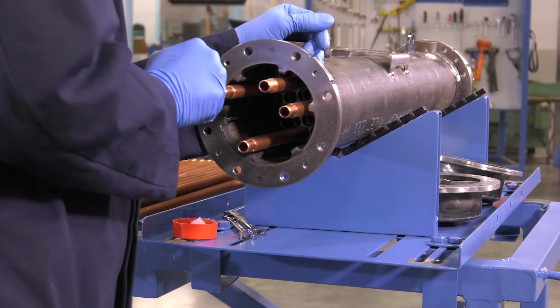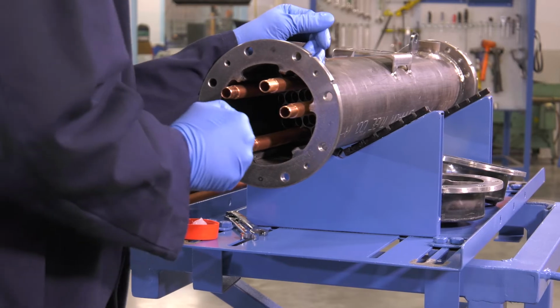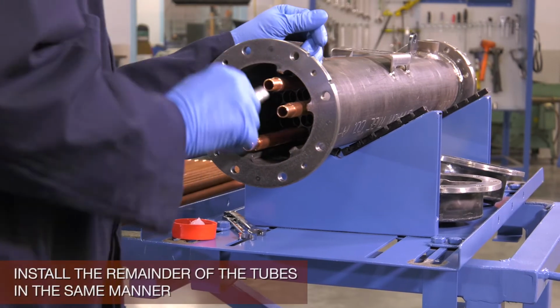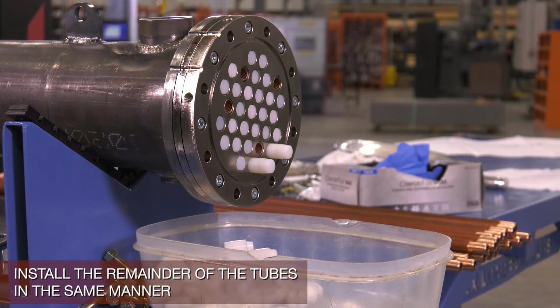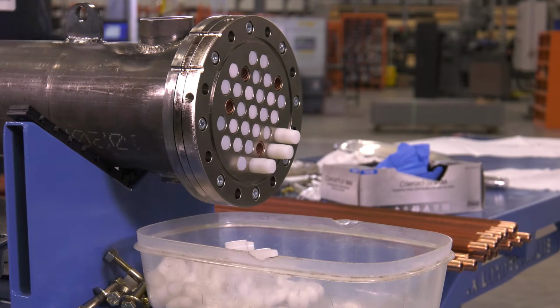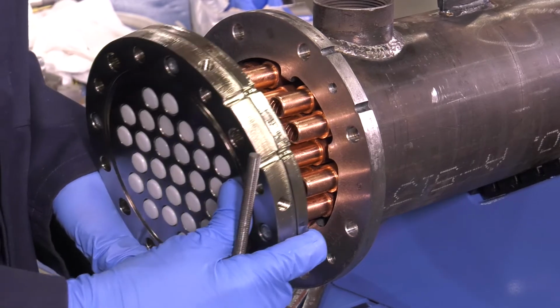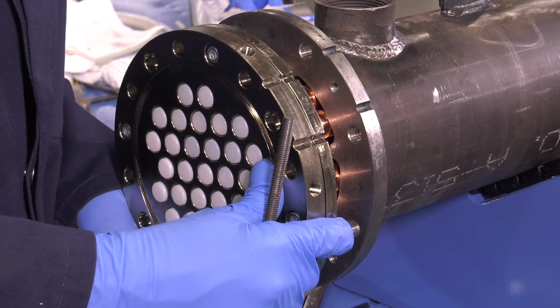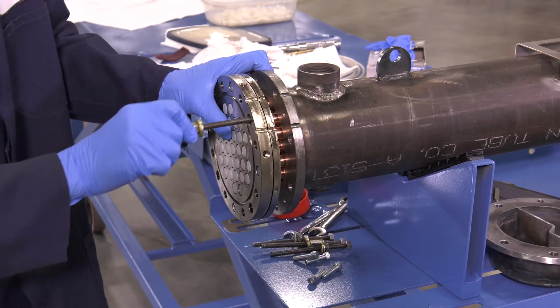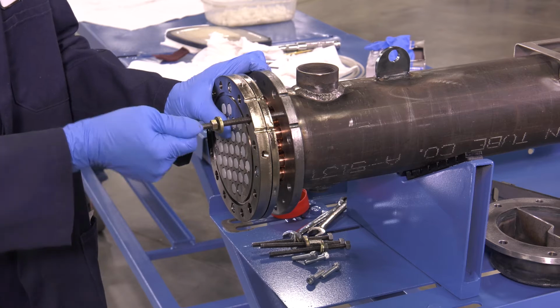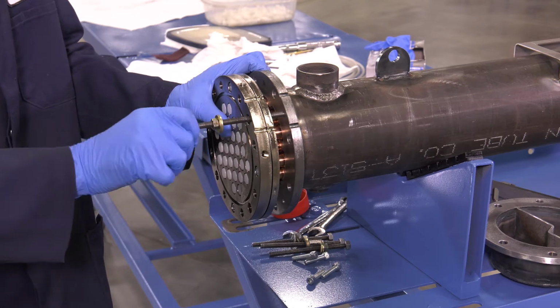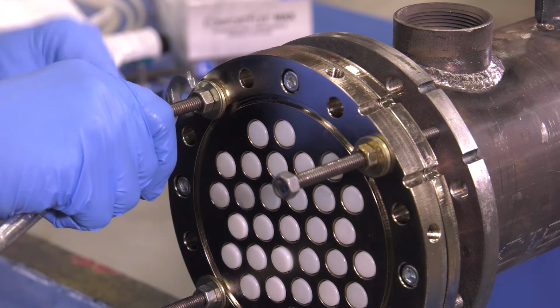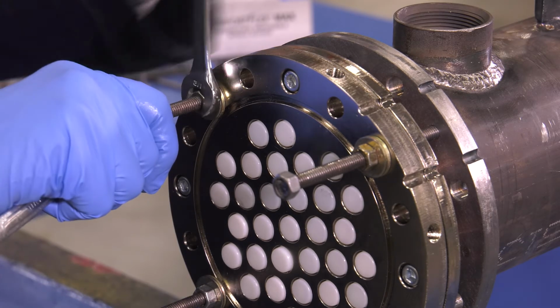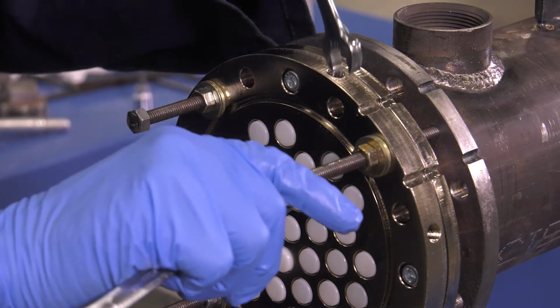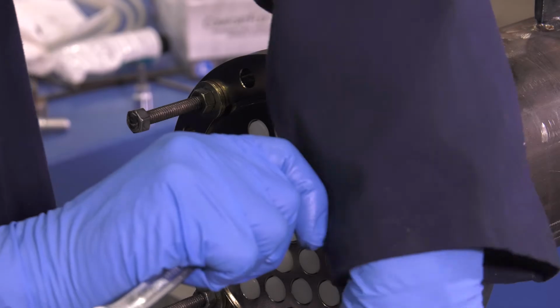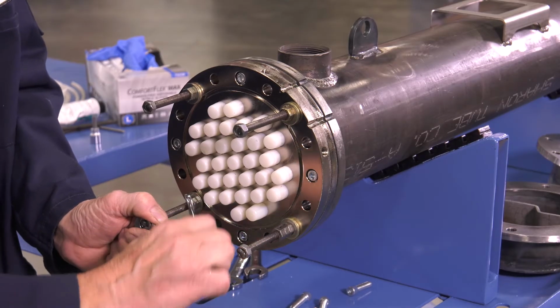Using the tube driver tool, push the tubes through the seals until the tube's shoulders bottom out on the header plate. This will push the plastic assembly bullets out of the header plate. Align the second header plate tube holes with the tubes, ensuring the orientation notches are lined up. Insert the header plate draw-down bolts into the header plate retainer bolt holes. Pull the header plate in place with the header plate draw-down bolts. Do this uniformly by alternately tightening each bolt around the perimeter, 1/2 turn at a time. Tighten until the header is tight to the shell.